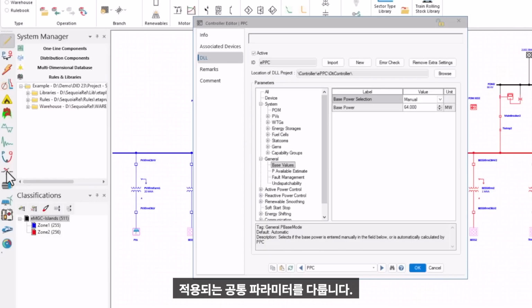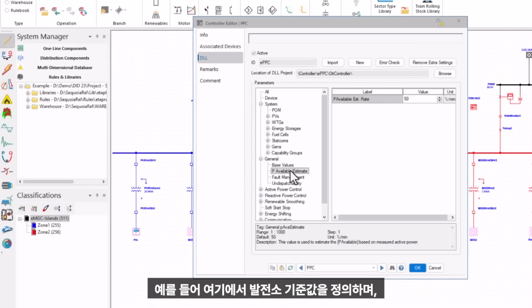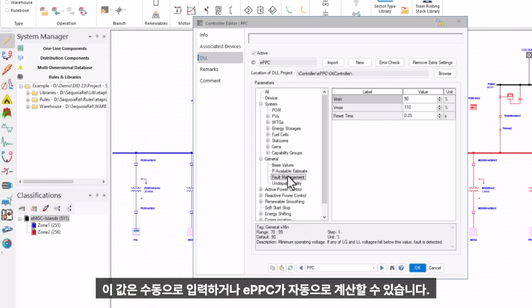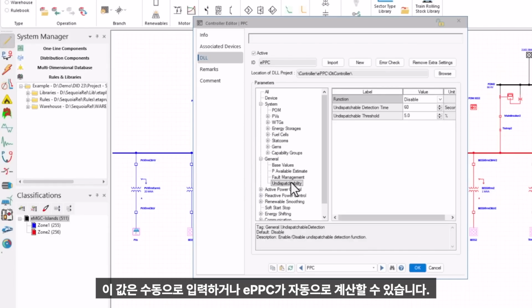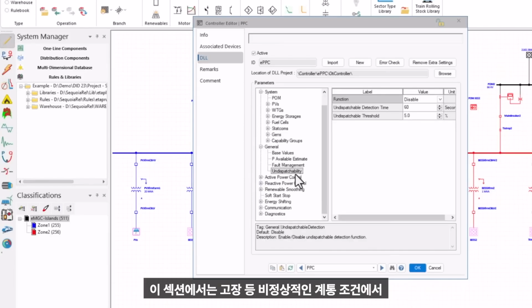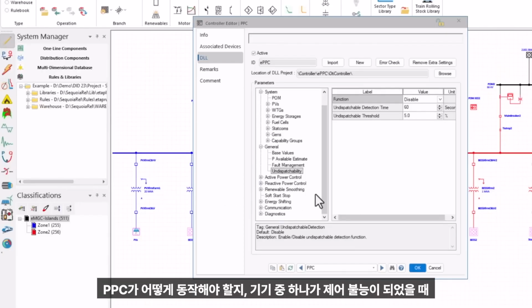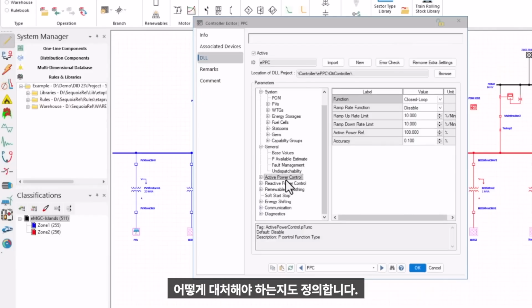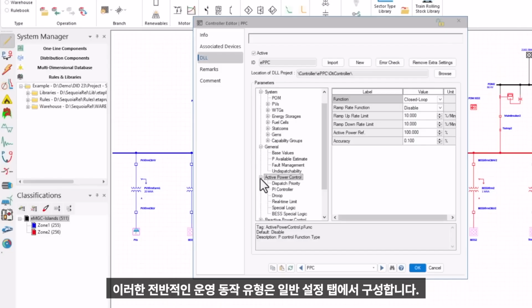The general settings section covers the more common plant-wide parameters. For example, this is where we define the plant base values, which can either be entered manually or calculated automatically by the ePPC. This section also defines how the PPC should behave during abnormal system conditions, such as faults, and how it should respond if one of the devices becomes undispatchable. These types of overall operating behaviors are configured under the general settings.